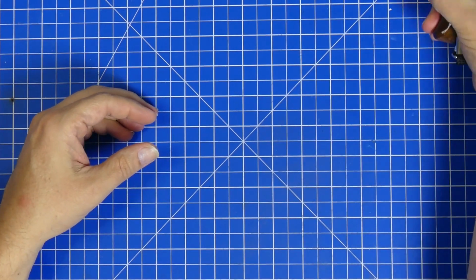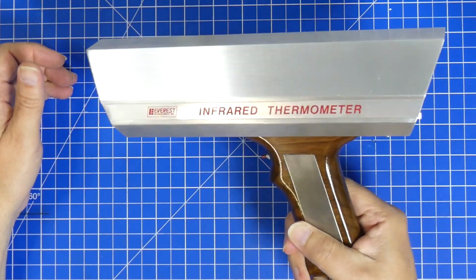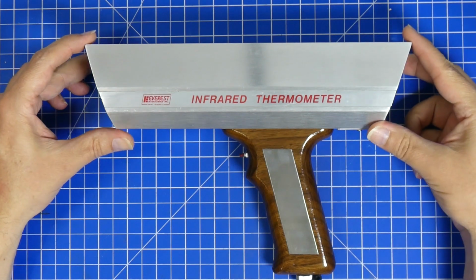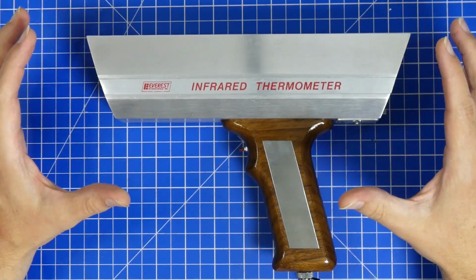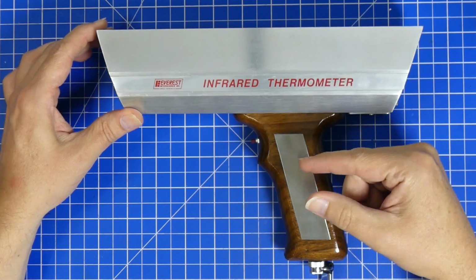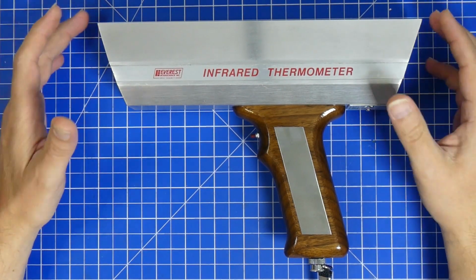My first digital imager, let's break out the big guns, is this one here. And believe it or not, this thing was incredibly expensive when it was new. These went for thousands and thousands of, back then, German marks. And they were really hard to get. And they were extremely expensive to keep running because they would need to be calibrated every year. And a single calibration of one of these was about 500 marks, which would translate roughly to about $1,000 today.